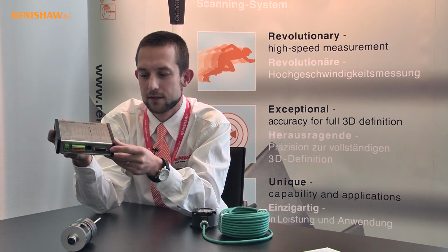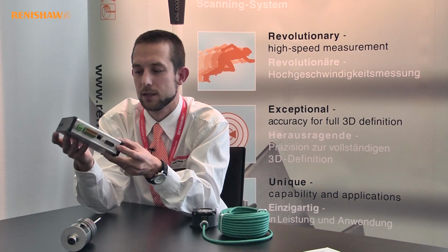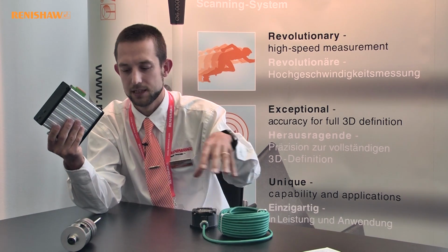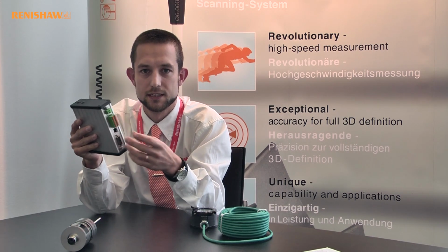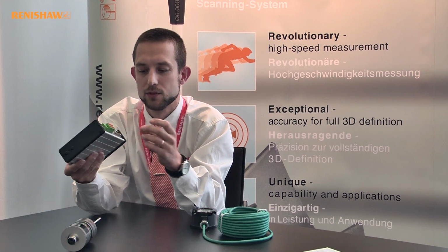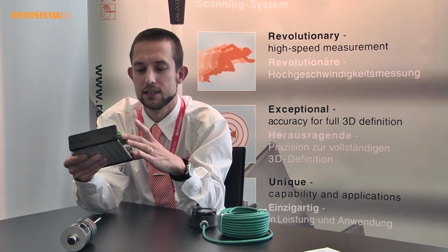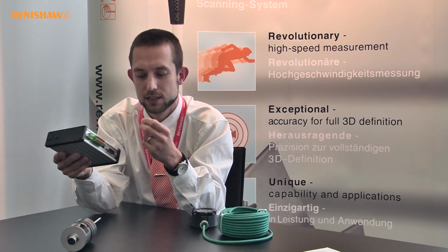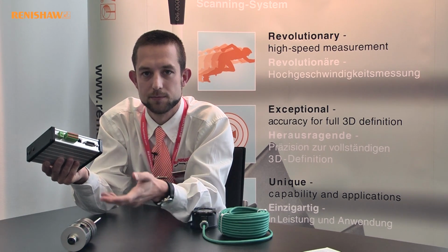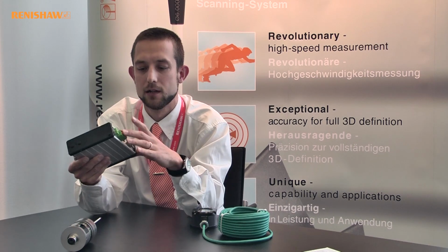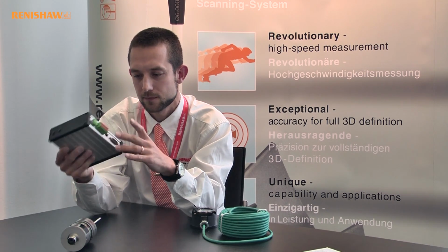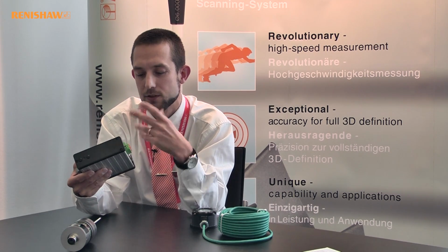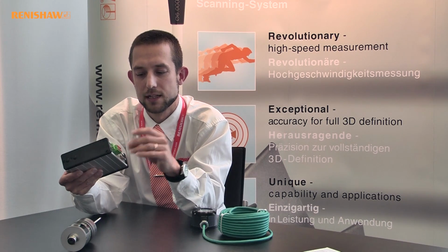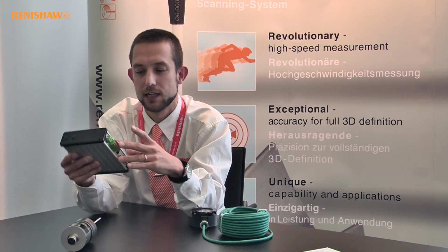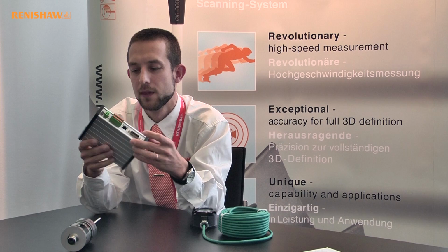This device is like the heartbeat that keeps the Sprint system running, because as well as collecting timestamp data from the OSP60, this device also synchronizes the data coming from the machine tool. So it has a dedicated connection into the CNC machine controller, and every time we collect a data point from the OSP60, we also collect in parallel a data point from the machine tool controller. This device deals with the clock signals for that, and it also has an Ethernet connection which allows it to communicate with the software component of the system.